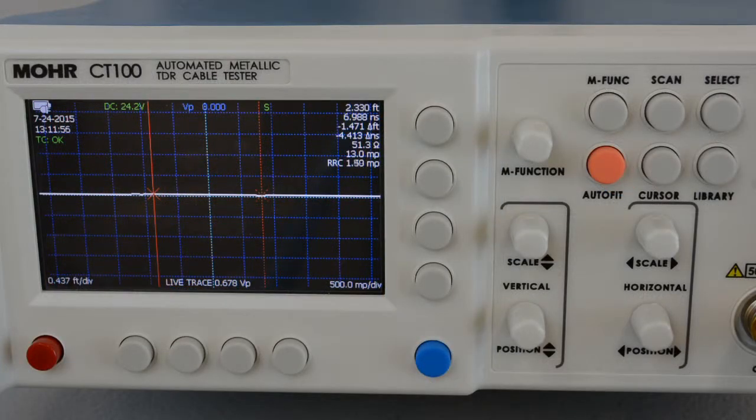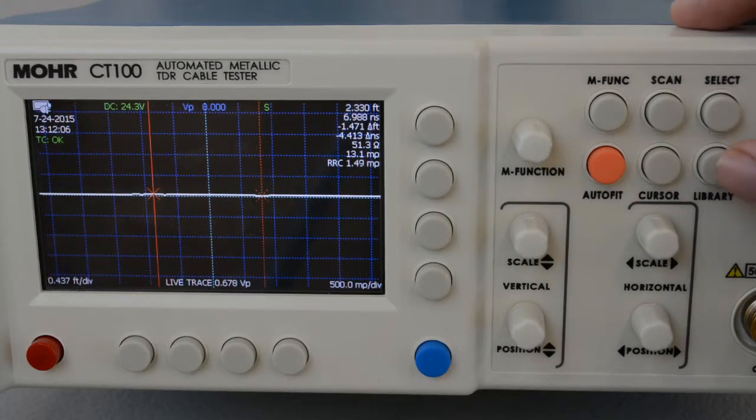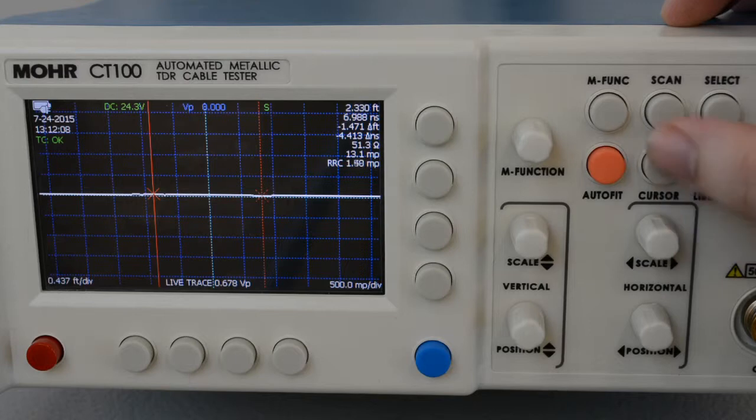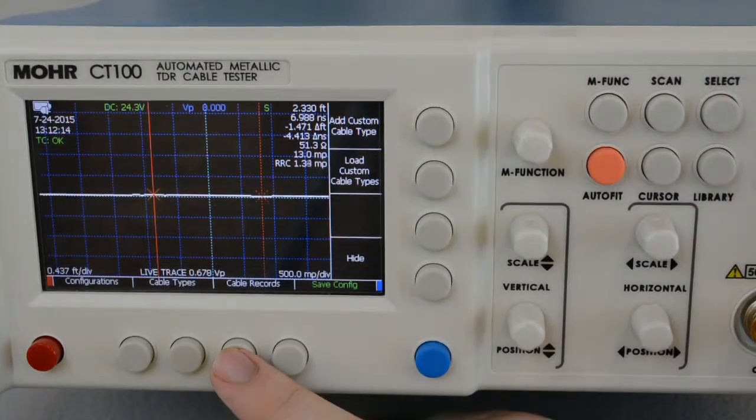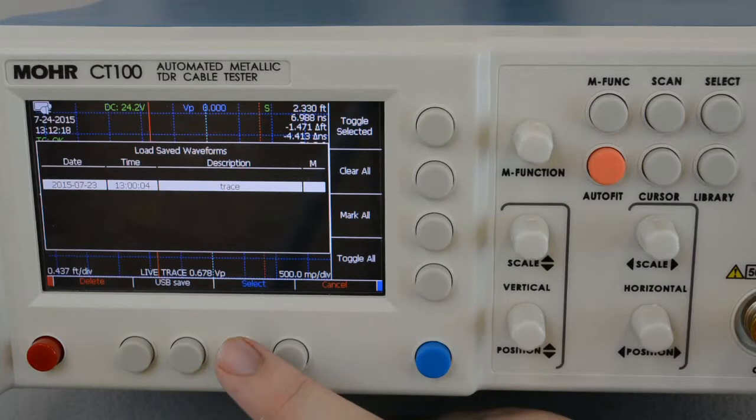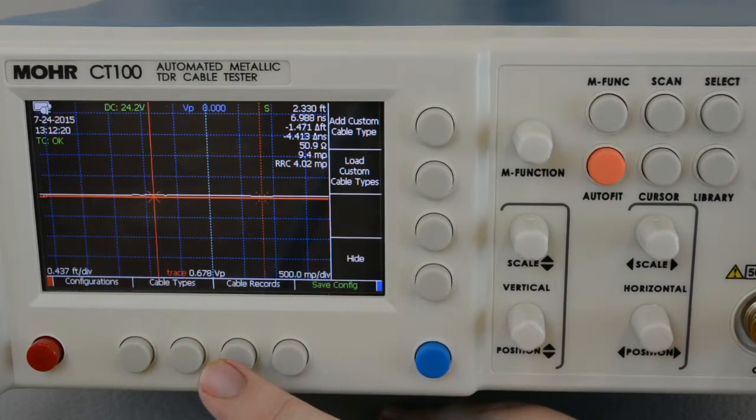Now I'm going to show you another application of the difference trace. The CT100 is currently scanning two cables that are connected via connector. I'm going to load a scan of the cable from when I know the connector was good. Now, I've loosened the connector just a half turn, so we're going to see if the CT100 can recognize that.